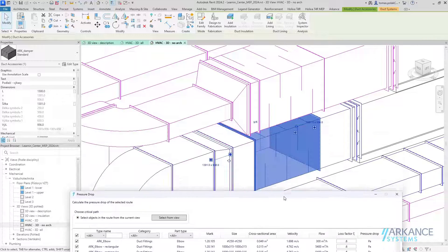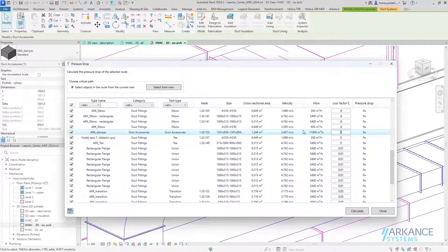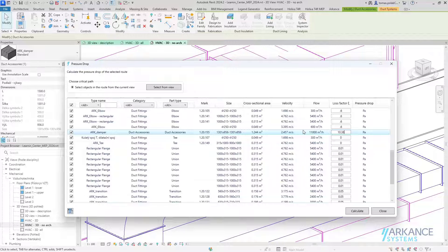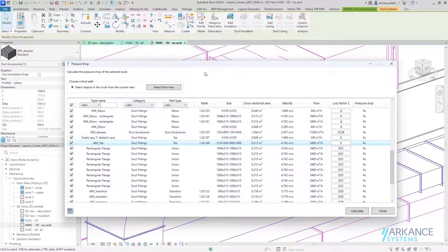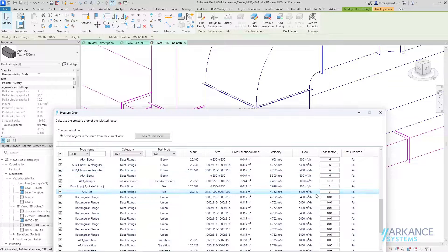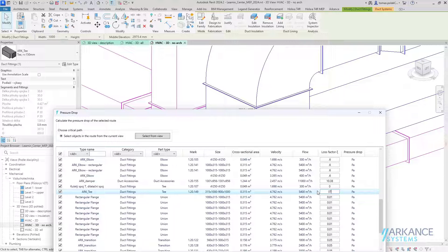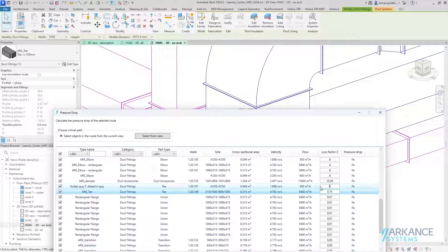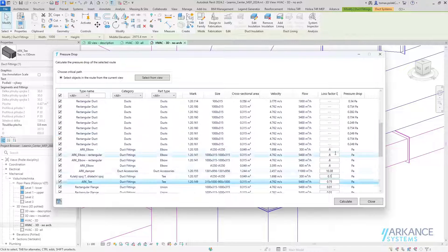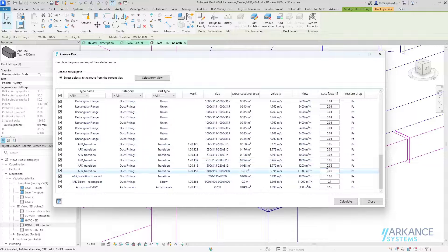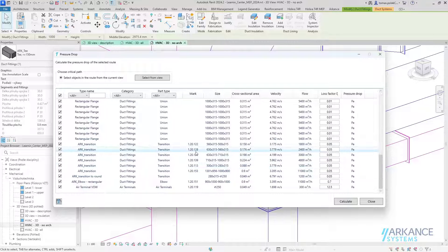One is the damper, so this one will have 10.38. This tee will have 0.75. Let me correct that value. This one will have 0.1. Now I've got all of the loss factors inserted for all of the instances.